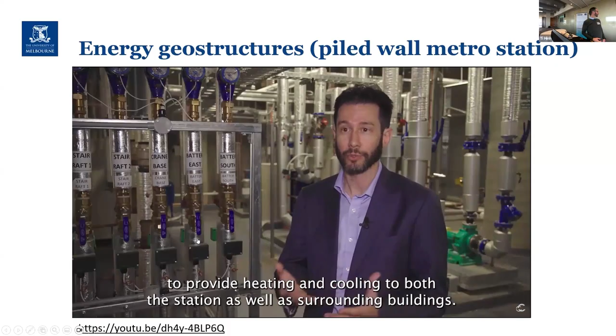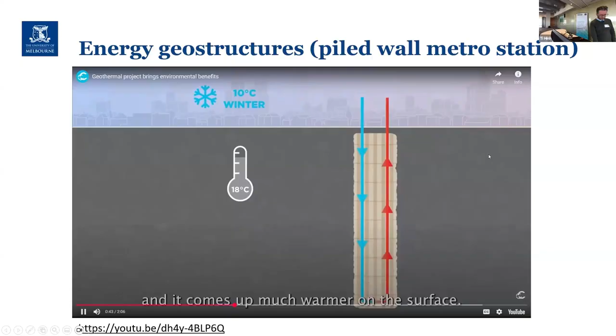In winter, say the air temperature is around 10 degrees, but our ground is at 18 degrees, much warmer. We inject water into pipes embedded in the retaining walls, and that water picks up thermal energy from the ground and comes up much warmer at the surface. Then the heat pump boosts it to provide heating to the buildings.